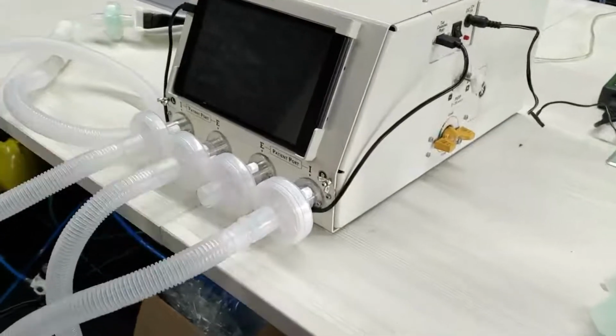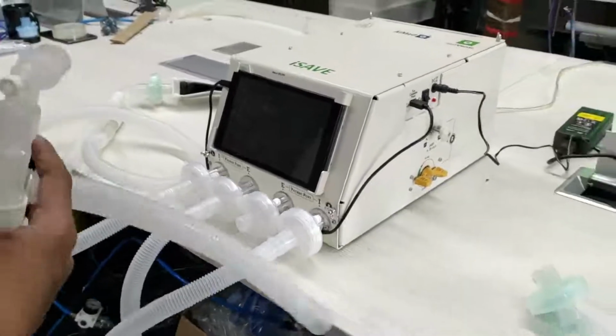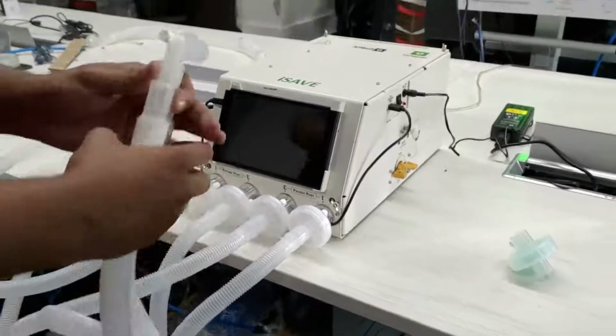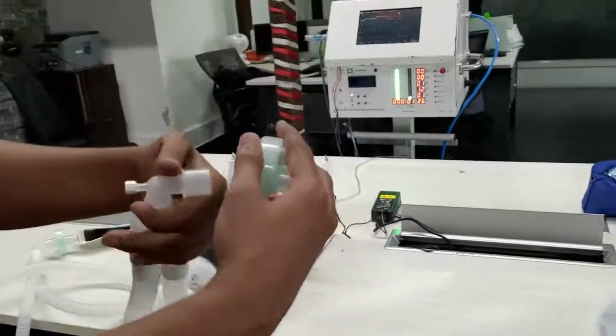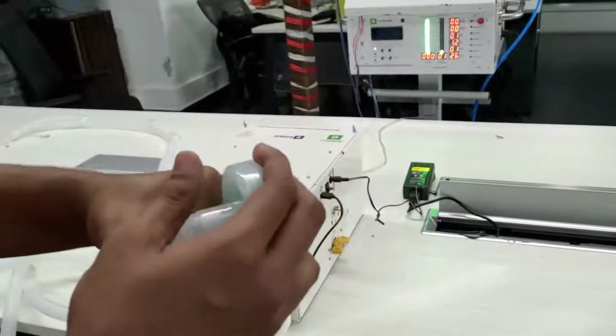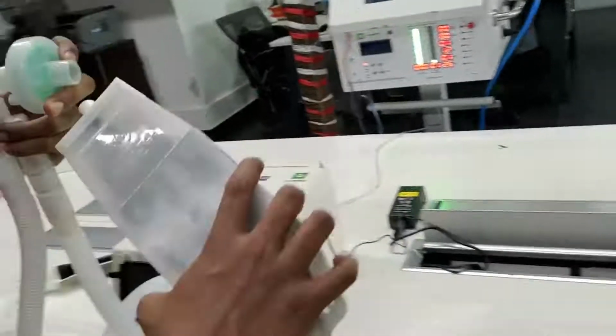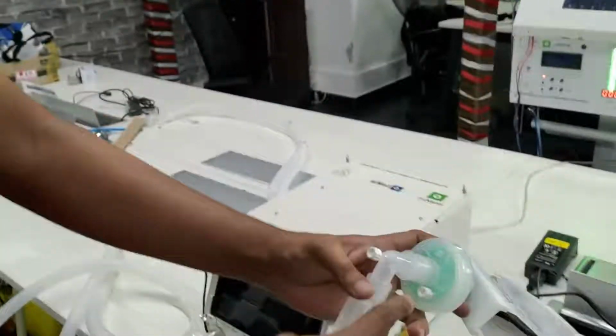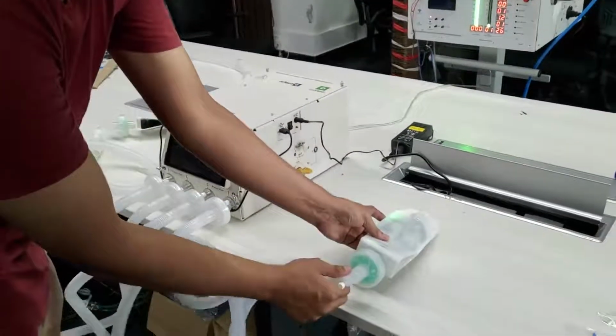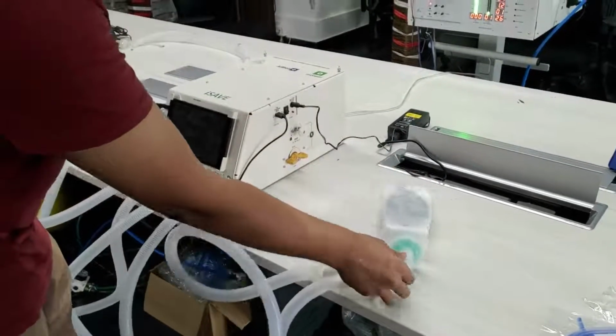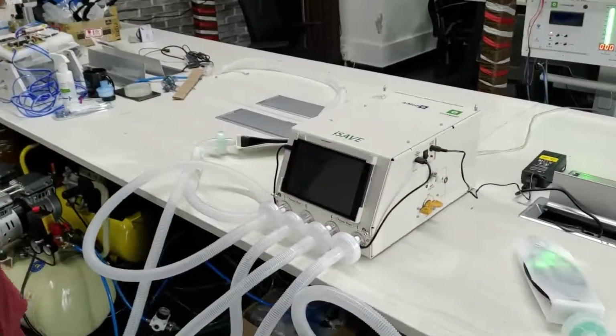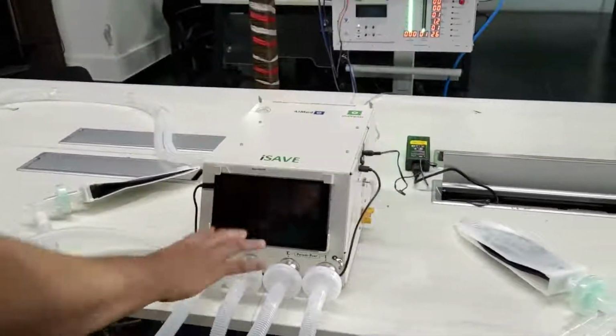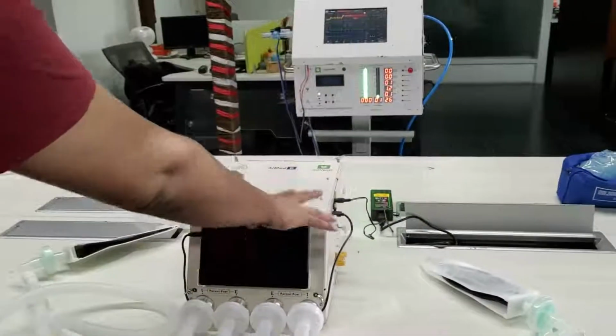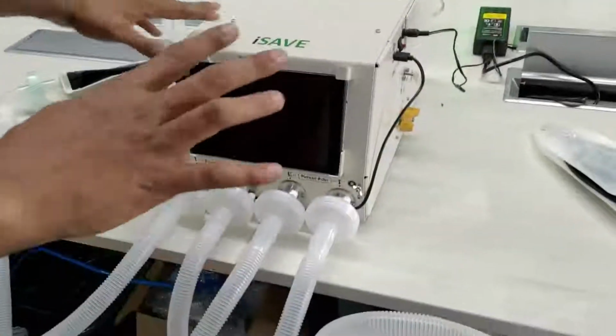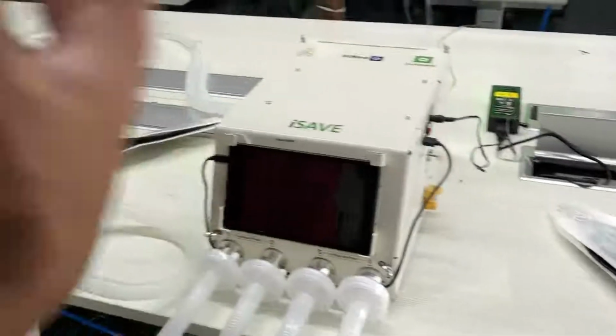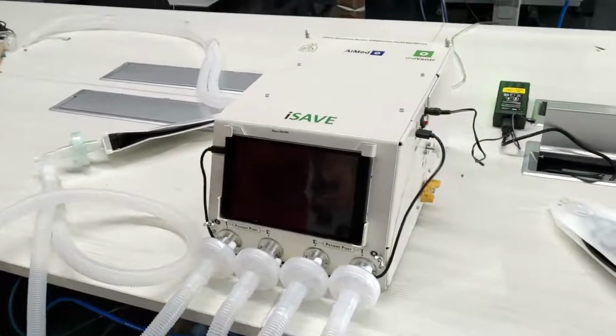Inspiration for the right patient, expiration for the right patient. Let's connect the BVF filter. Let's put the patient lung. Again, make sure all of these are capped so that there's no leak in the circuit. If there is a leak, we do have alarms that will come up in the iSAVE. All these filters are needed so that we don't contaminate the insides of the iSAVE, and also to prevent any contamination or exposure to the air that may occur.